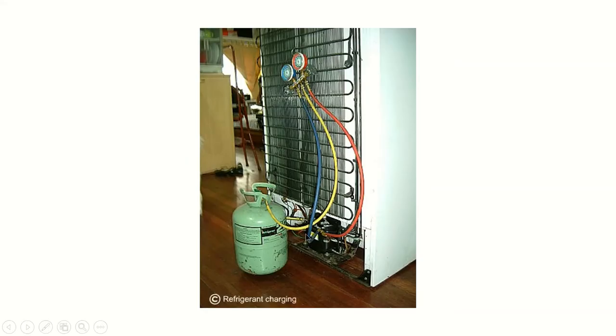Okay, so here is a diagram showing us how the recharging is done. As you can see right here, the auxiliary, which is the yellow hose, goes into the refrigerant cylinder, while the red hose goes to the high side of the system and the blue goes to the low side. So the refrigerant comes in from the yellow hose, which is the auxiliary, and goes through the blue hose to recharge the system. Most times when we are recharging, we recharge through the blue hose into the system.